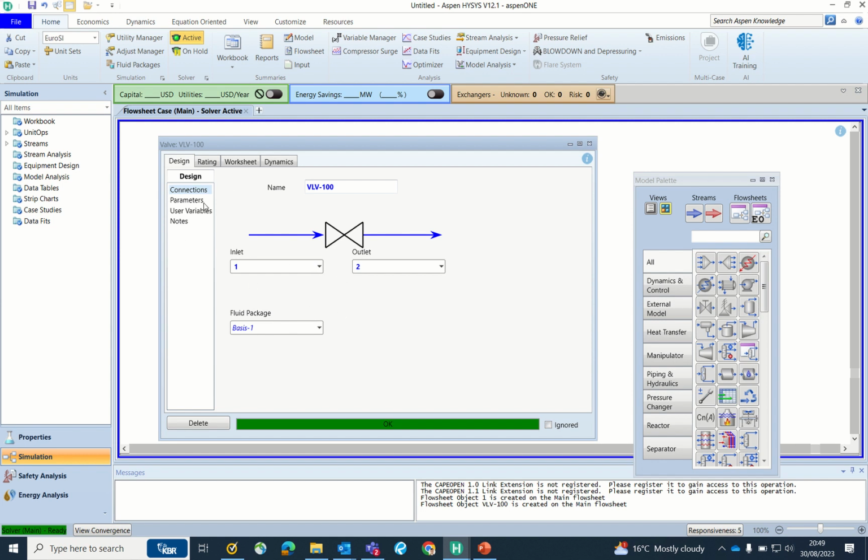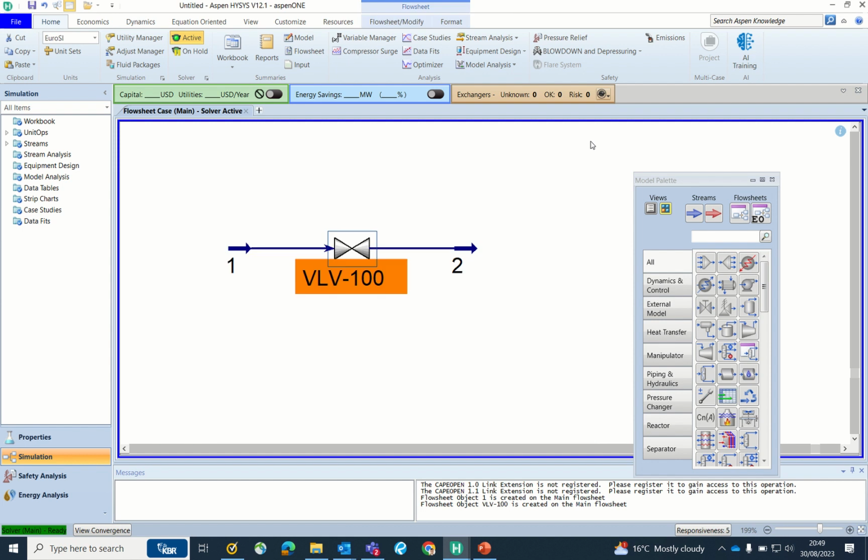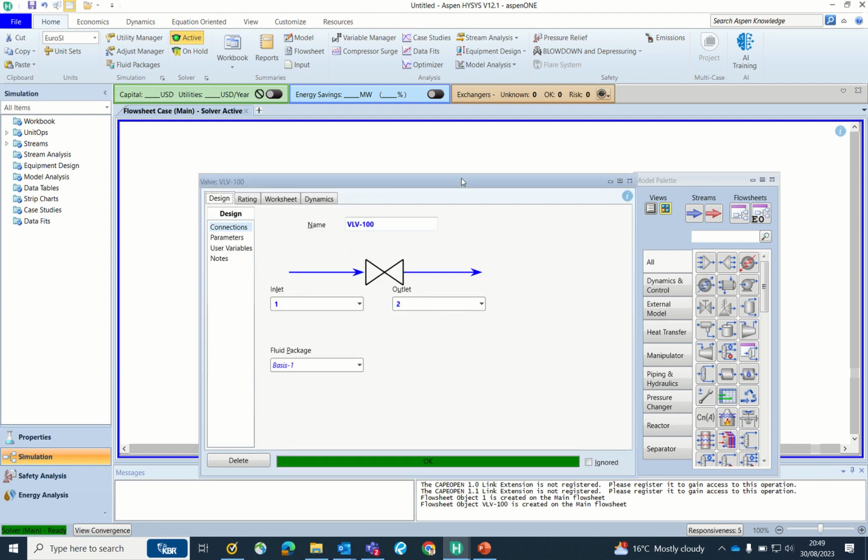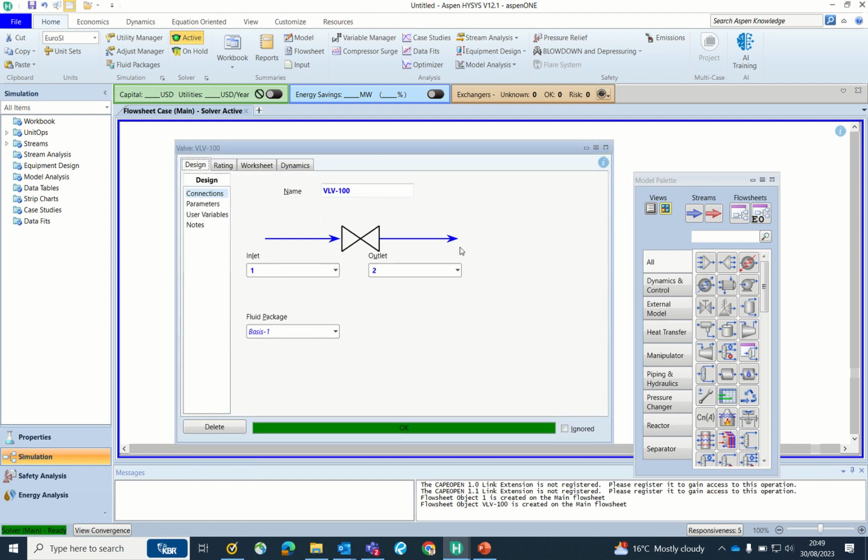As you can see, the parameter we have defined is 0.7, which is an arbitrary value actually. If you don't want to define that, you can also decide what the final pressure should be, and subsequently the control valve can calculate how much dp is across the line. So it is just a basic video. For more hydraulics, you can put a pipeline segment over there, and also here, to decide how much pressure drop is in the line and how much pressure drop is in the control valve, right?